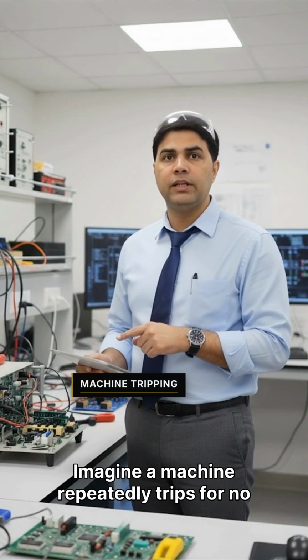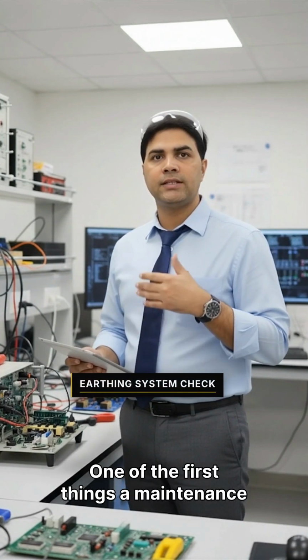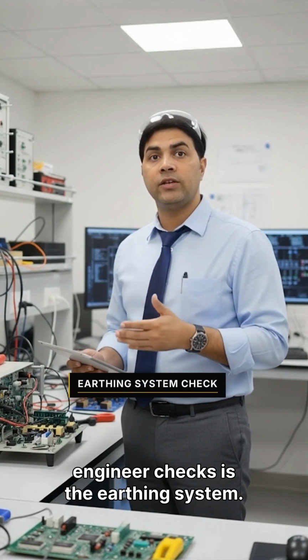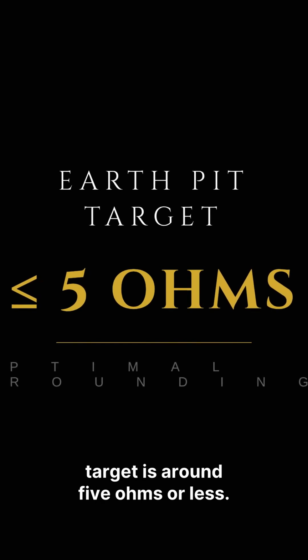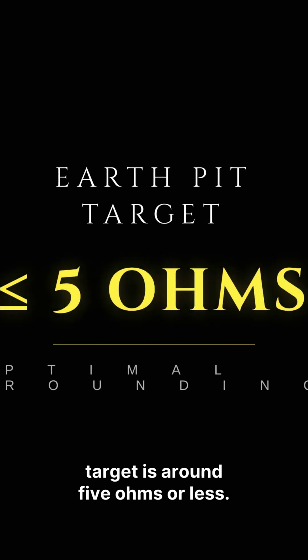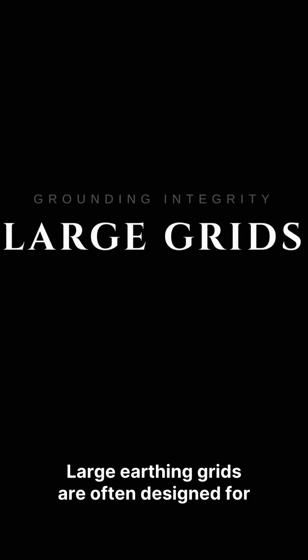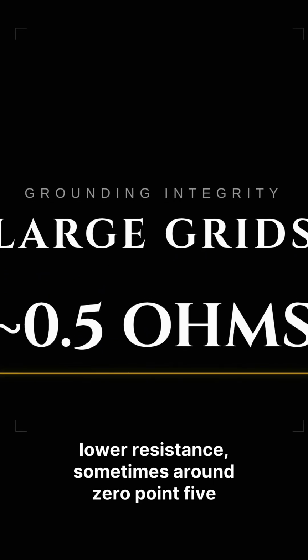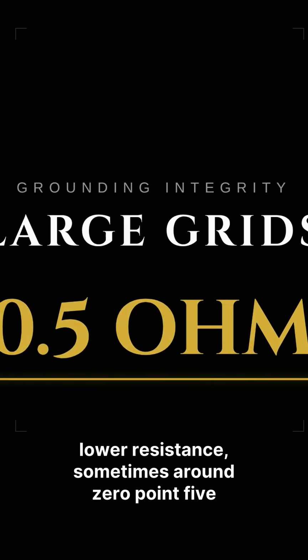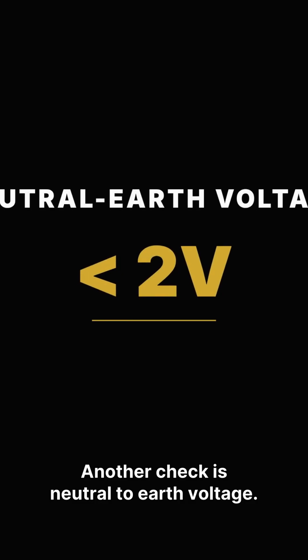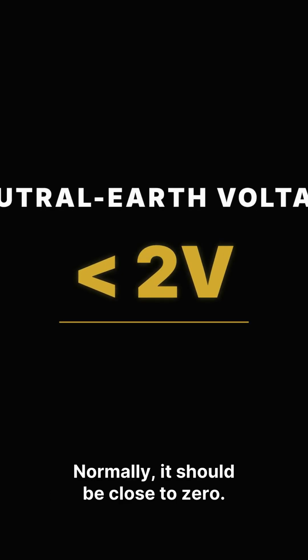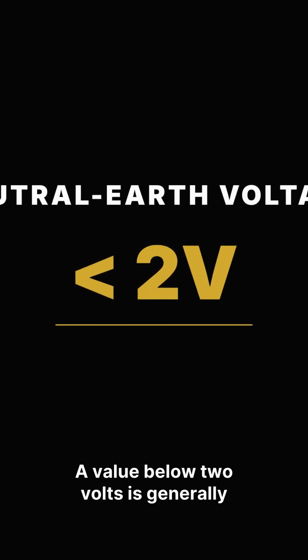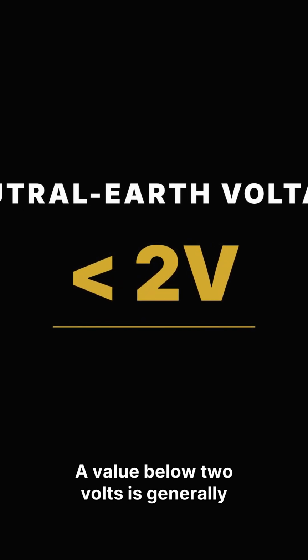Imagine a machine repeatedly trips for no obvious reason. One of the first things a maintenance engineer checks is the earthing system. For industrial installations, a single earth pit target is around 5 ohms or less. Large earthing grids are often designed for lower resistance, sometimes around 0.5 ohms. Another check is neutral to earth voltage. Normally, it should be close to 0. A value below 2 volts is generally acceptable.